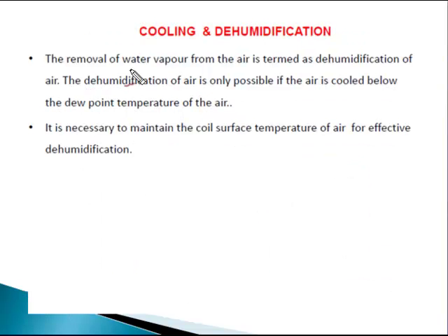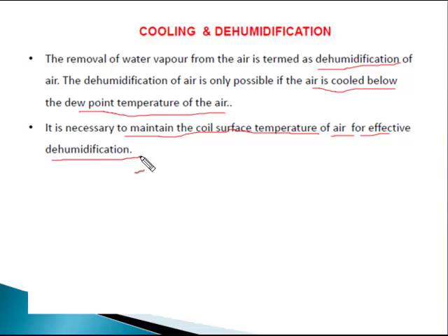The removal of water vapor from the air is termed dehumidification of air. The dehumidification of air is only possible if the air is cooled below the dew point temperature of the air. It is necessary to maintain the coil surface temperature for effective dehumidification.